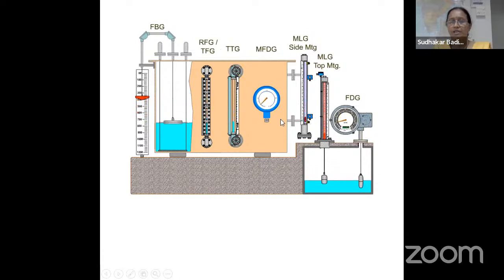This is a side-mounted magnetic level gauge. Inside the chamber, there is a magnetic float. As this magnetic float moves, this capsule also moves along with it, and you can read the liquid level corresponding to this capsule position. Then this is a top-mounted magnetic level gauge and a float and dial gauge, which are installed on a sump or underground tank. In the top-mounted magnetic level gauge, you can see the level indication through the flapper indication. And in the float and dial gauge, you can read the liquid level on the dial through this pointer.